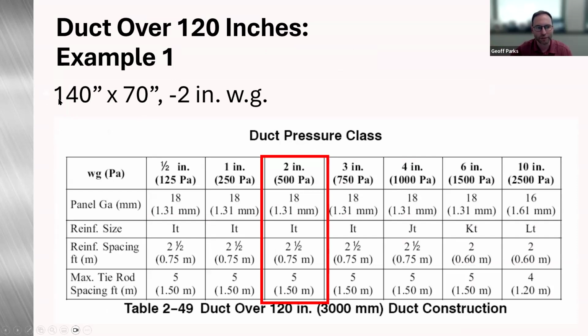But example one, if we have a 140 by 70 at 2-inch water gauge, we would come to table 2-49 and get our 2-inch water gauge. Sorry, I've got phones ringing, things dinging, I apologize. Our panel gauge is going to be 18. Our reinforcement size is going to be an IT. Our reinforcement spacing, again, 2.5 foot. And then our tie rods.